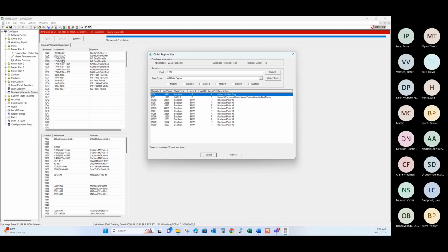Right. So if the meter is not active, 1105 is going to be a 0. So I send the opposite of that 0 to 1736. So the opposite of 0 is a 1. So 1736, when I set it to a 1, it's going to disable meter 1, right?